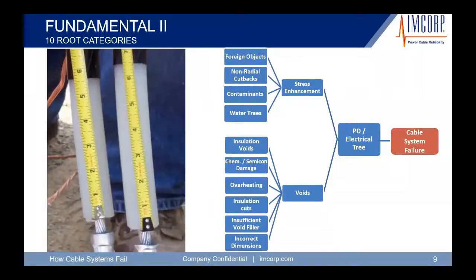Okay, and then here's our most common issue. The improper cutback dimensions on terminations as well as splices. Remember, a splice is nothing more than a couple of terminations. The way the components are designed today, you have to make a perfect cutback so that the stress control mechanism sits right over the semicon and insulation interface. And it has to put a lot of pressure on that as well.